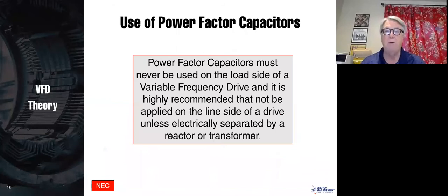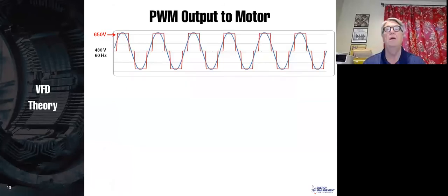You should never use power factor capacitors on the load side of a drive unless you'd like to buy another drive. Now here is your output to the motor. Now you can turn it on positive or you can turn it on negative, and thus you get an AC waveform. Now this is 650 volts, and therefore when you turn it on positive, you're always going to get 650 volts because that is the voltage on the DC bus, or negative 650 volts. Now we put 480 volts 60 hertz in, we get 480 volts 60 hertz out. We didn't really accomplish much.